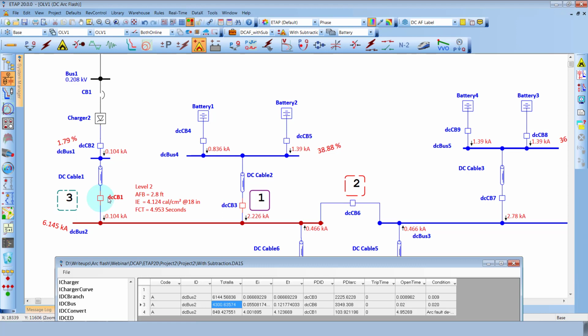And in the third stage, from fault clearing time 2 to 3, it is assumed that the contribution from the charger alone is added to the incident energy calculation, which in turn constitutes the third stage of the incident energy. And at the end, all the incident energy calculations that are calculated per stage are added to give the final incident energy value at a given working distance and the last protective device clearing time.